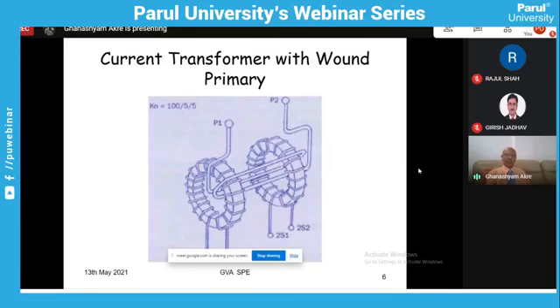In practice, the core which you have seen as rectangular is not rectangular in a current transformer, but actually toroidal in shape, round. I will explain why that is so in future. Here you see the two toroidal cores having secondary windings, 1S1, 1S2, and 2S1, 2S2. And there is a common primary from P1 to P2 having two turns. So this transformer is a wound core primary.